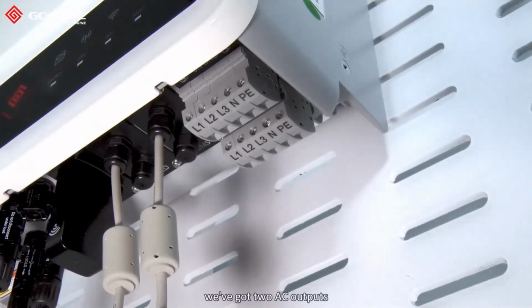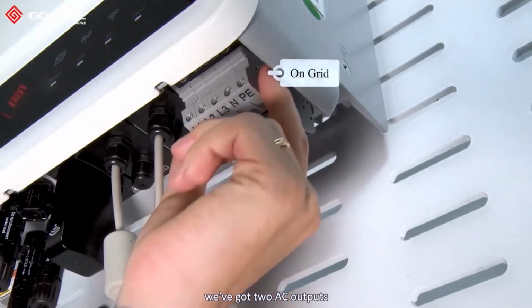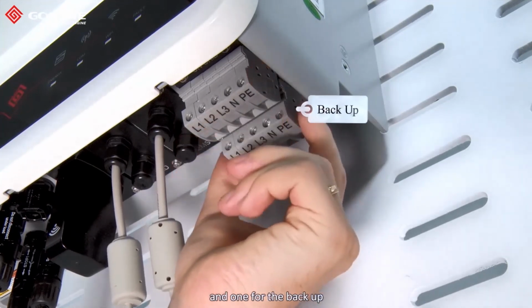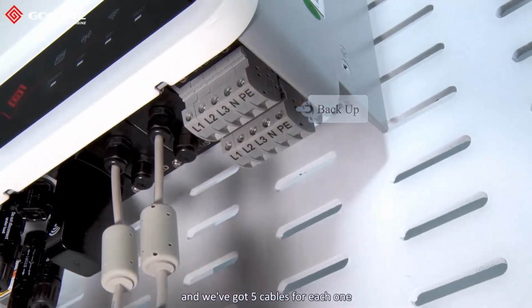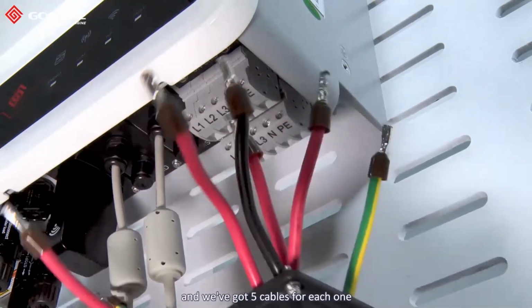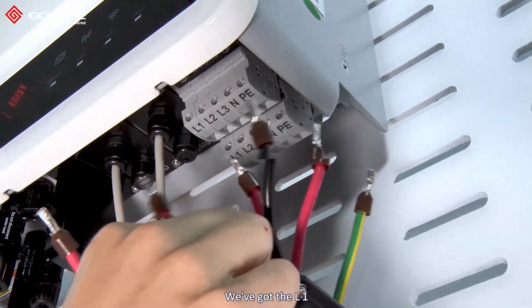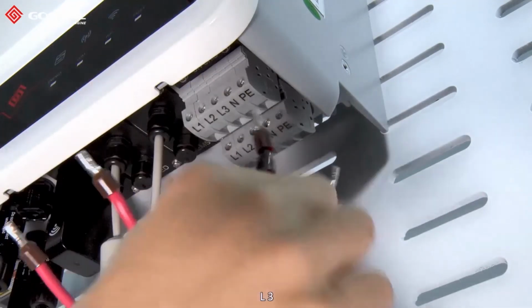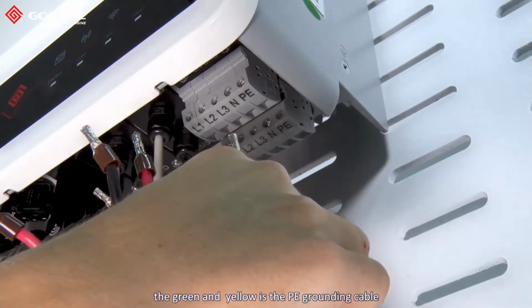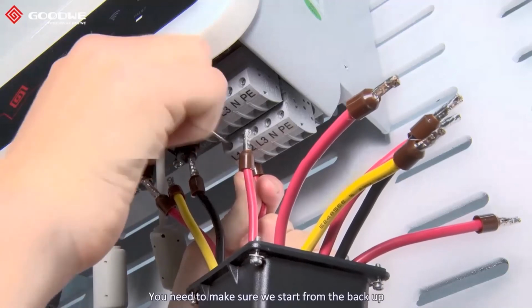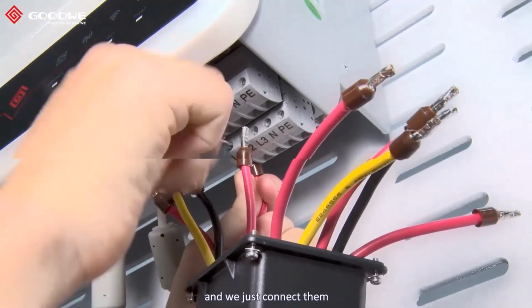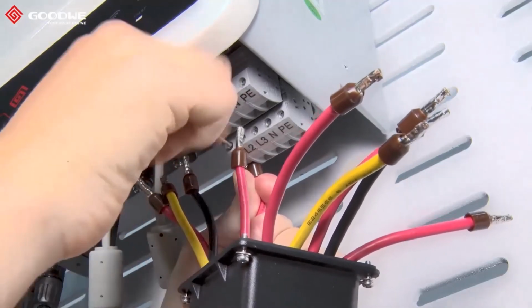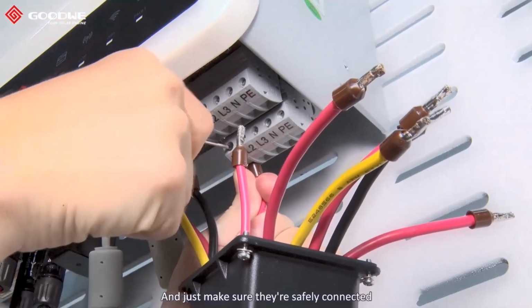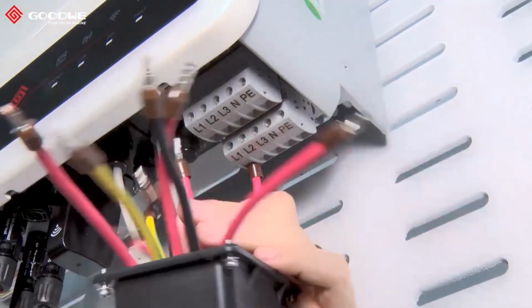As we just mentioned, we've got 2 AC outputs, one for the on-grid and one for the backup, and we've got 5 cables for each one. We've got L1, L2, L3, the black one is the neutral cable, and the green and yellow is the PE grounding cable. You need to make sure we start from the backup, and we just connect them like so, and make sure they're safely connected.